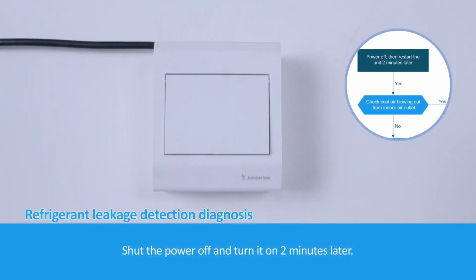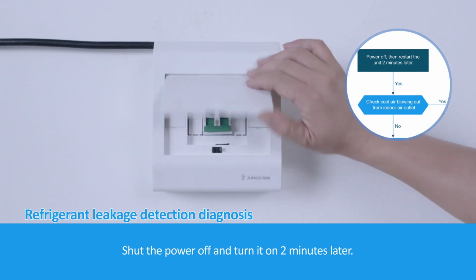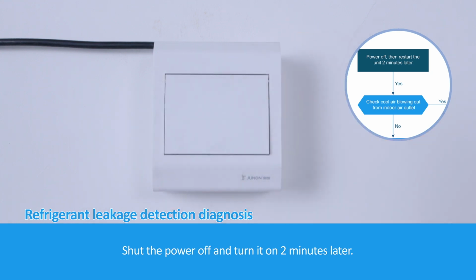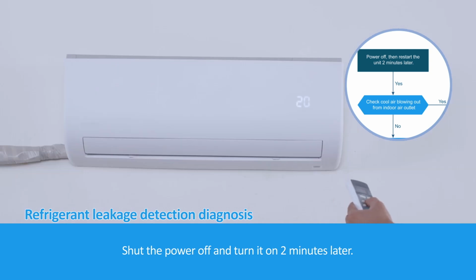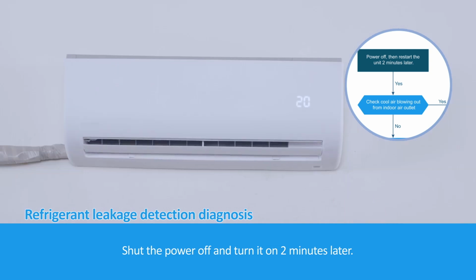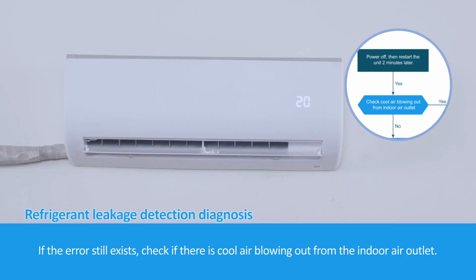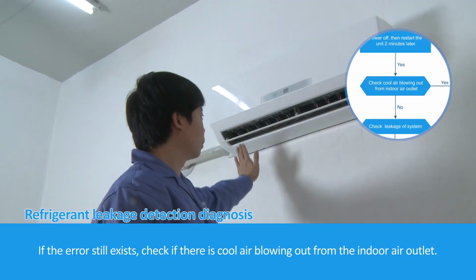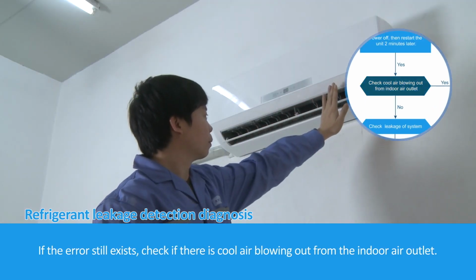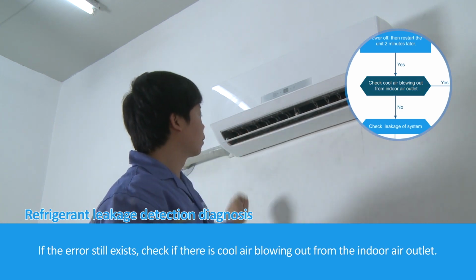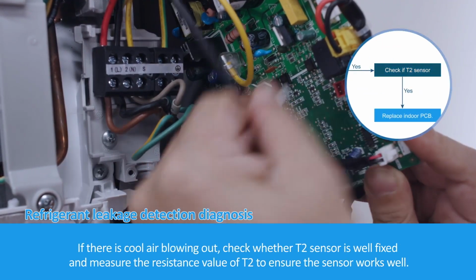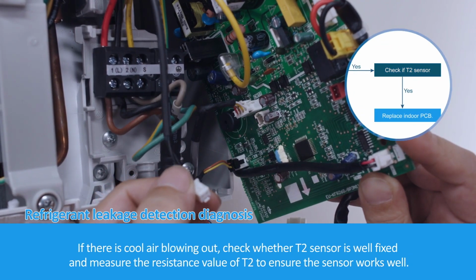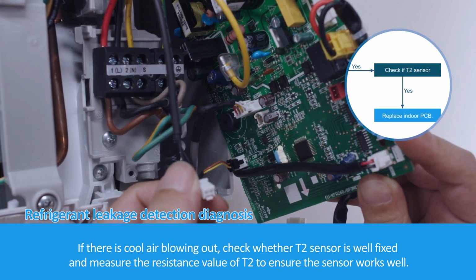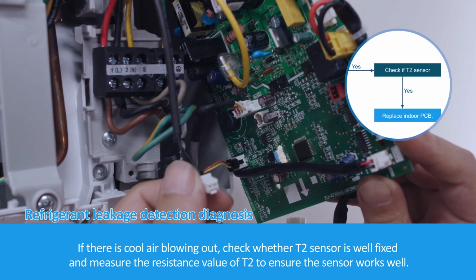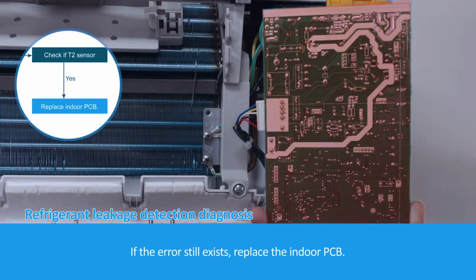Shut the power off and turn it on 2 minutes later. If the error still exists, check if there is cool air blowing out from the indoor air outlet. If there is cool air blowing out, check whether T2 sensor is well fixed and measure the resistance value of T2 to ensure the sensor works well. If the error still exists, replace the indoor PCB.